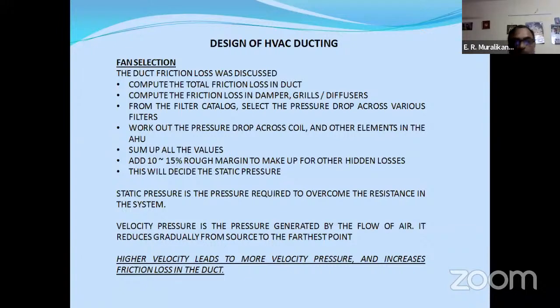This will decide the static pressure. This static pressure is the required pressure to overcome the resistance in the system. Velocity pressure is the pressure generated by the flow of air. It reduces gradually from the source to the farthest point.